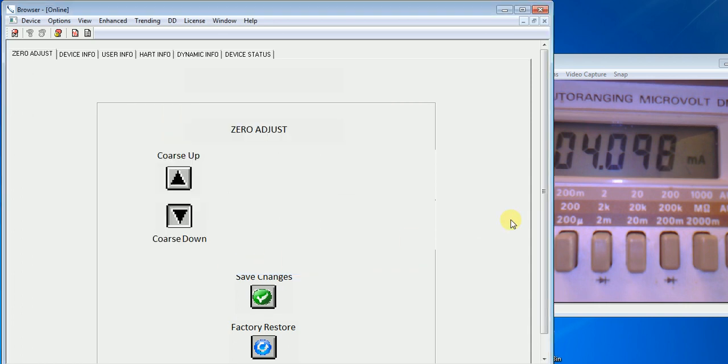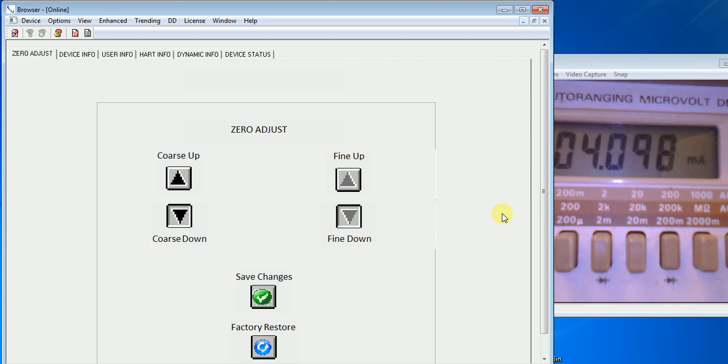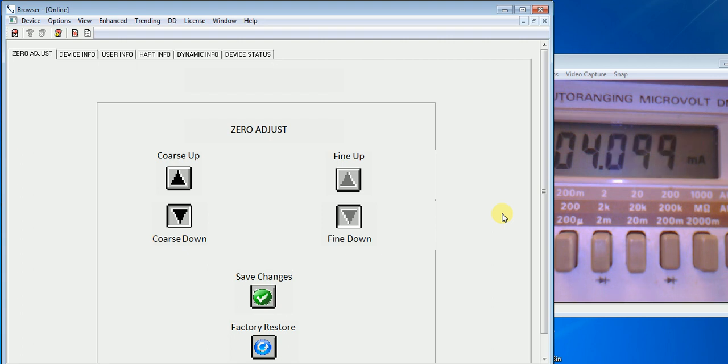Now when I power the unit down, it will remain at 4.098 milliamps. So I will quickly do that. You'll see the reading go away on the meter and then come back to 4.098. So there we are. We're right back where we started again. That's because we saved the changes.